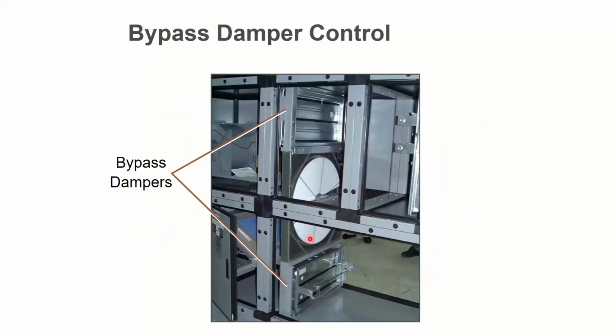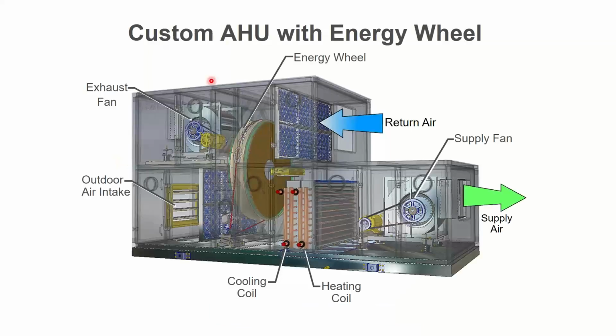In this case, I have a wheel in here that's rotating between the two, and one airflow is going through this way. The other airflow path is going through this way. And then the ERV wheel is rotating between the two of them, transferring the BTUs. We do have bypasses on this one, because when it's an economizer day, I want to open up the fresh air intake damper a lot more than normal to suck in lots of extra cool free air. Well, in that case, I don't want to recover my building heat and dump it into the incoming air because I literally want cold air. I'm asking for it. When I ask for an economizer, I want cold air. So I don't want to preheat it by accident. So I open up these bypass dampers and shut off this wheel in this case to let all the airflow skip the heat exchanger for those economizer days.